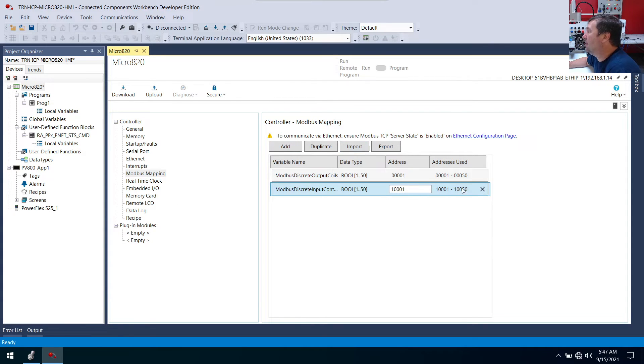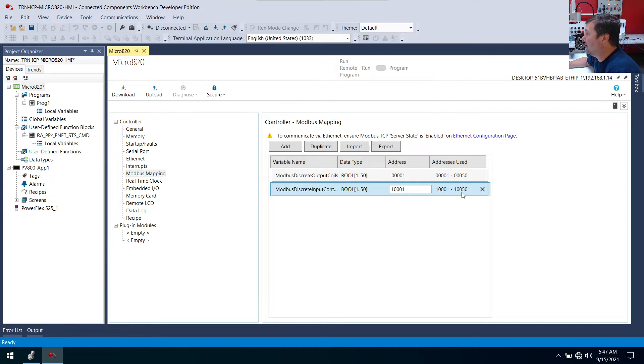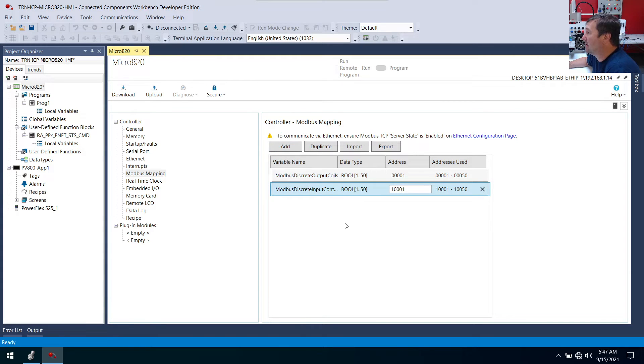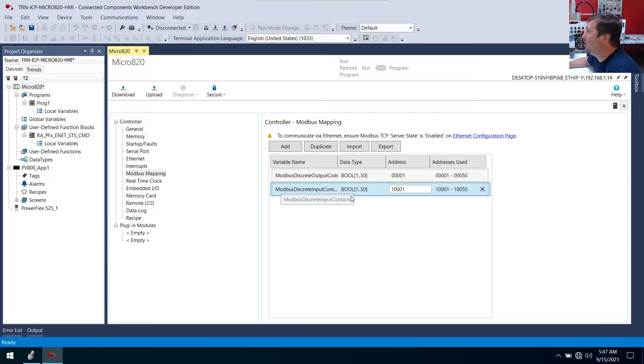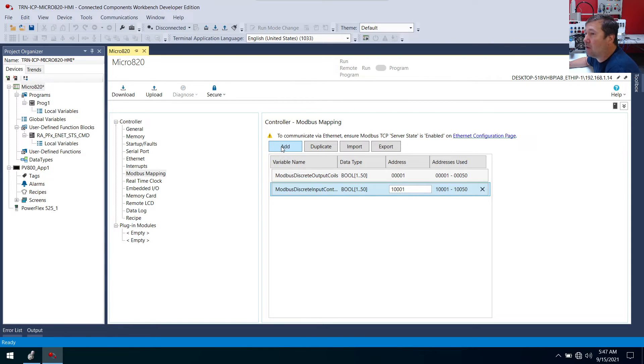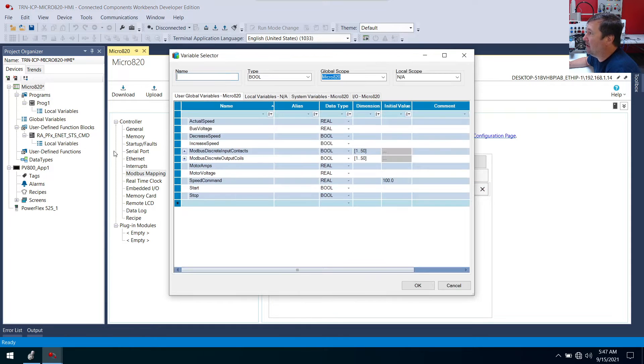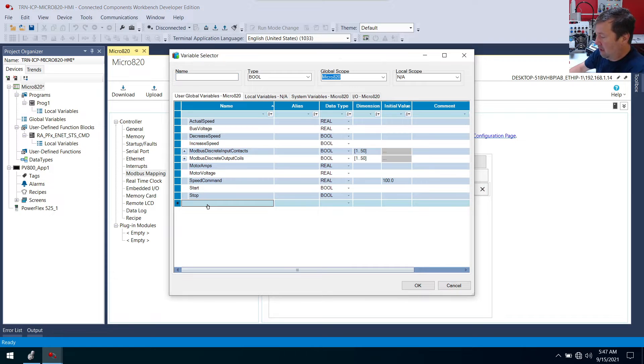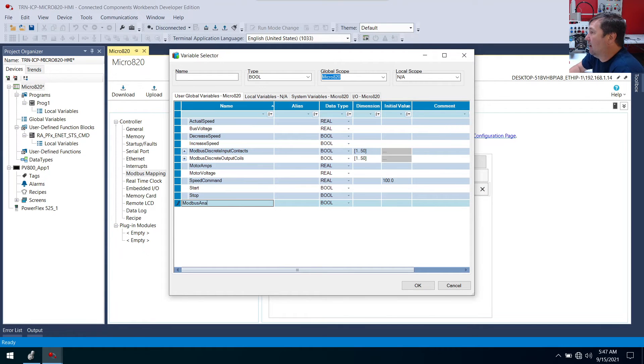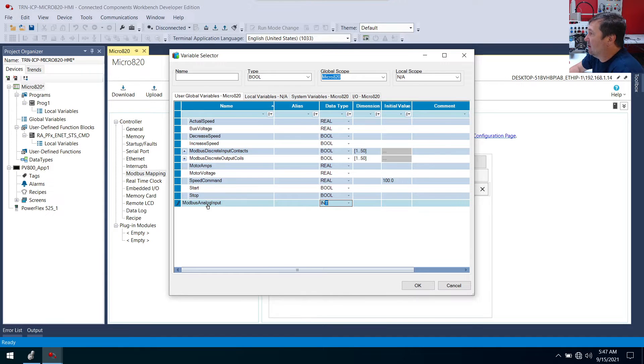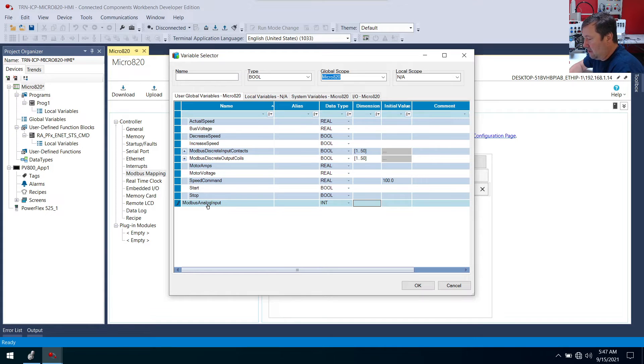So this will give us some basic flags, such as you press a button, we could pass a button on over, or we could see that an output's turned on. But also we want to pass data across, maybe an analog signal, a count value, something like that. So we're going to create some integers now. And we're going to create modbus analog input. And in this case, this is going to be an integer. And we are going to make this also a dimension of 1 through 50.